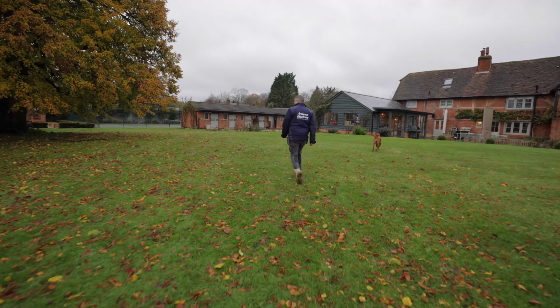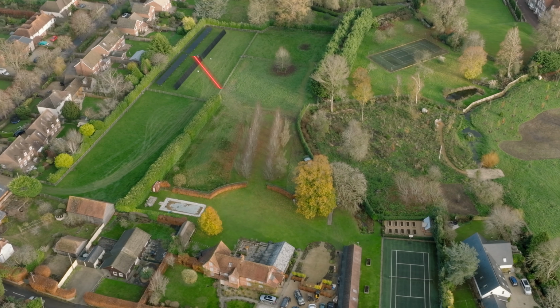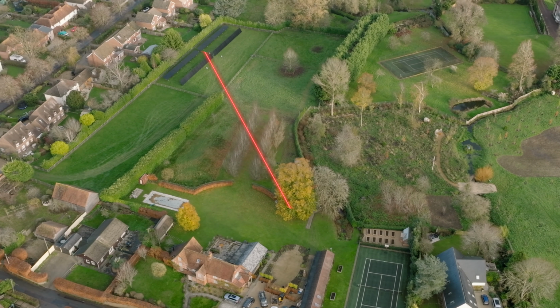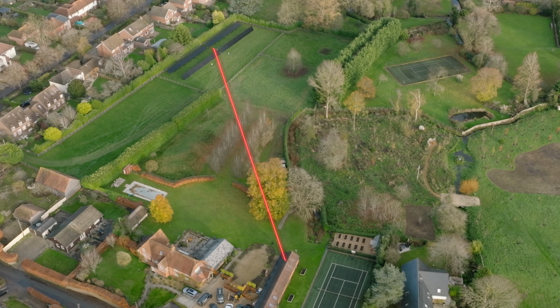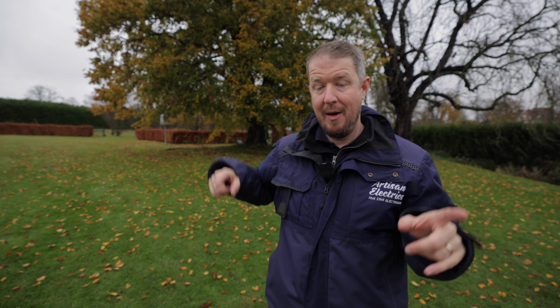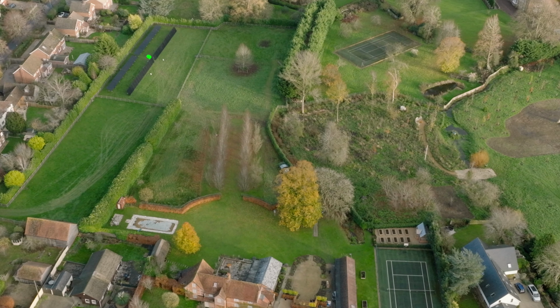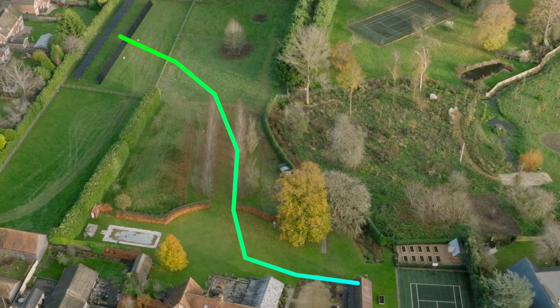So this is the tree that has caused us the most headaches. The original plan was to keep the cable route as short as possible to reduce DC voltage drop, going straight between these two trees with the installation. However, one of the conditions on the planning application was that we needed to route around the tree to avoid any possible root damage, and that added another 20 meters of cable to the run, which adds up to 80 meters across the 4 cables. Luckily, we managed to get it done.